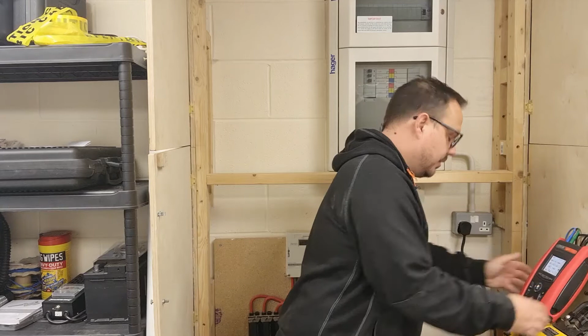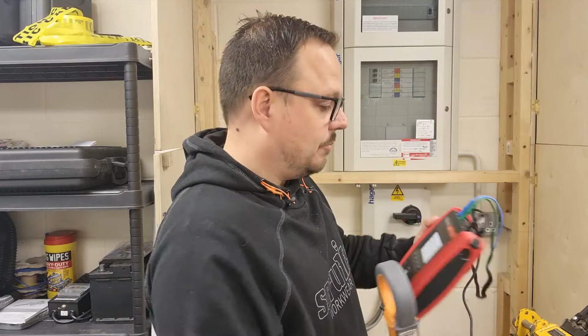So as soon as I take that off, I come back and show you this test set for power quality analysis. It's not going to show you any information to do with the current or what's been consumed unless you've got the clamp. So the clamp just pops in the back there, and I'll show you how that connects and disconnects a bit later on in the video. So I just pop that back down on there, and we go back around the L2 conductor, and you can see straight away it's popping up with the 2 kilowatts again and the power factor of 0.99.